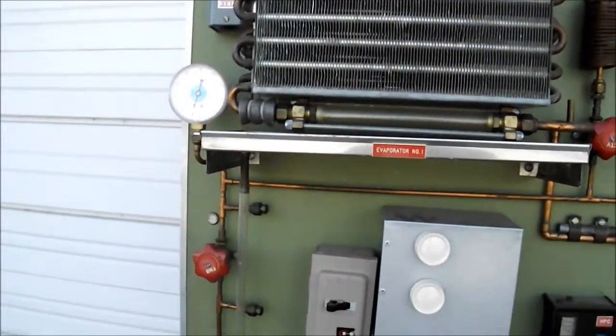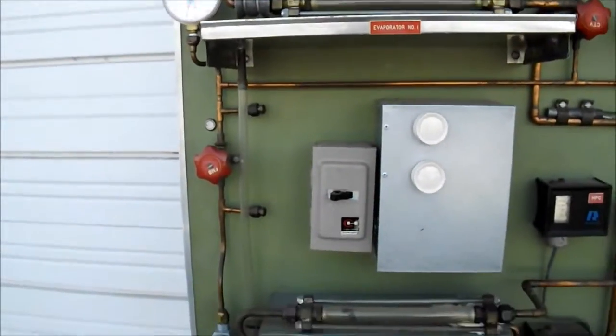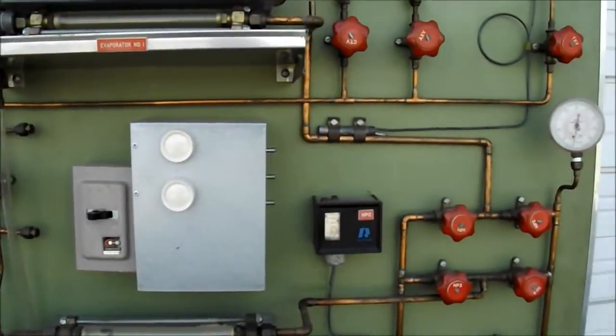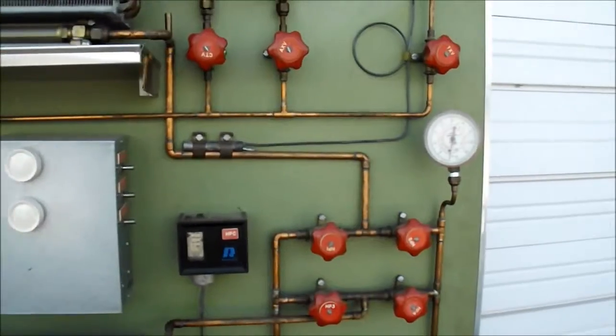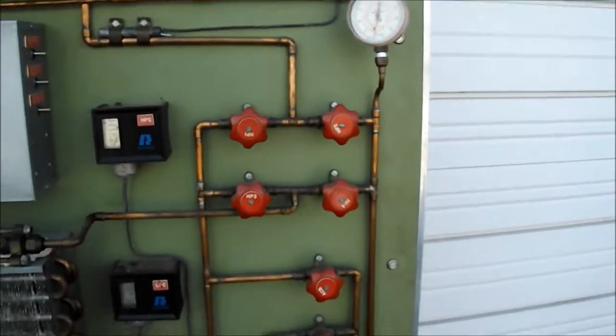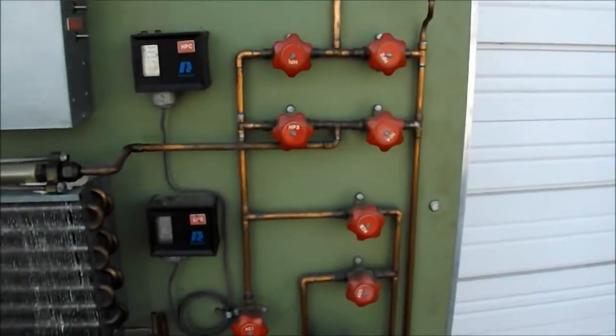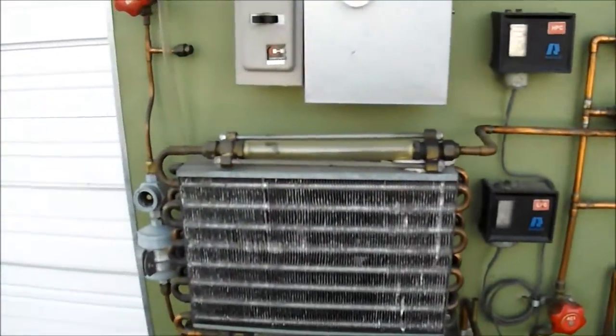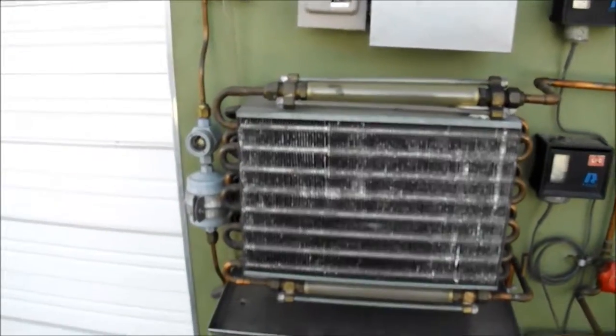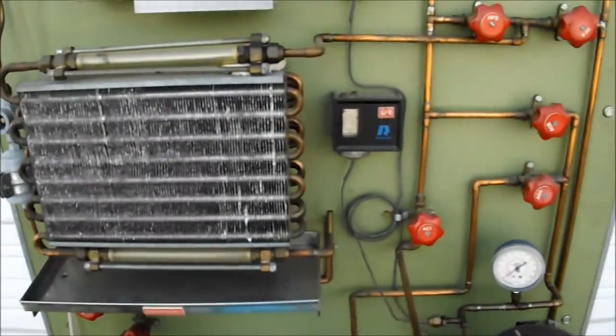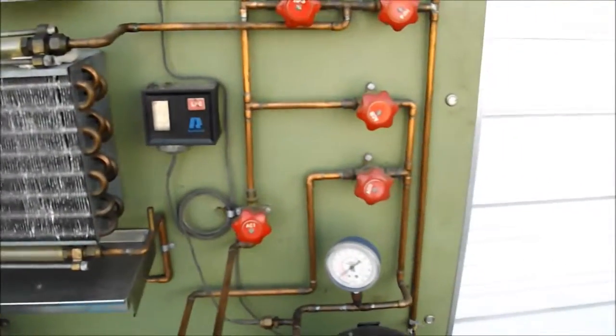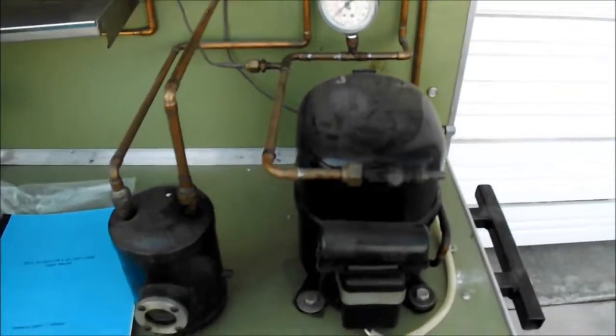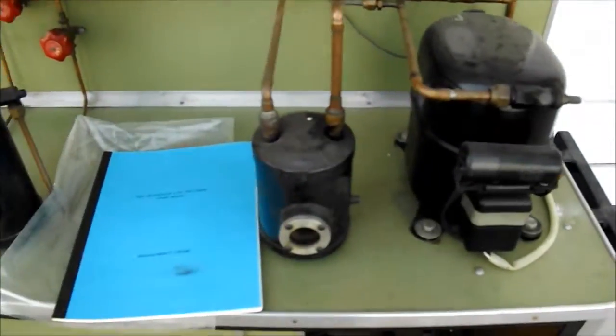The refrigerant was removed, oil removed, and flushed, and the synthetic oil put in so that the remainder of the mineral oil is less than 5% with a refractometer.